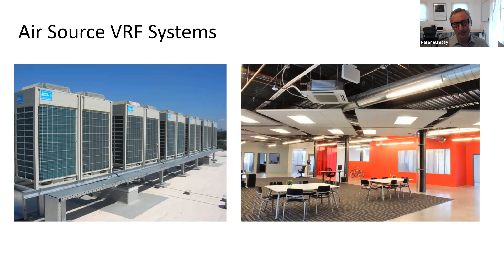The interesting thing about VRF systems is they're multi-zone, so you could have one zone in heating and another zone in cooling. In fact, they have a way through the refrigerant to move some of that heat from the area that's in cooling and put it into the area that needs heating. So it's a very interesting and efficient system.